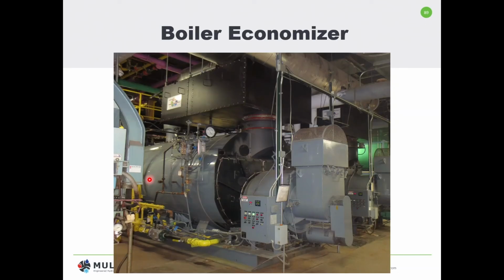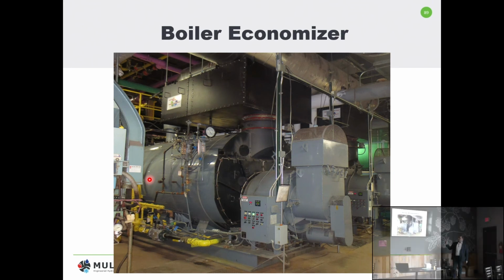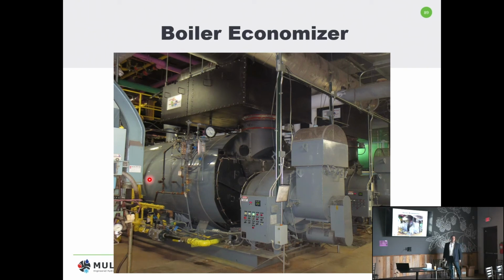So, lastly, a couple of things that we've done, retrofits we've done to systems, is boiler economizers. Here we're trying to capture the lost stack heat in the system. We could use that heat to either preheat water going into the boiler or dump into another load altogether. You could actually take an old-fashioned 80% steam boiler at 80% efficiency and jack it up to the condensing efficiencies through one of these.